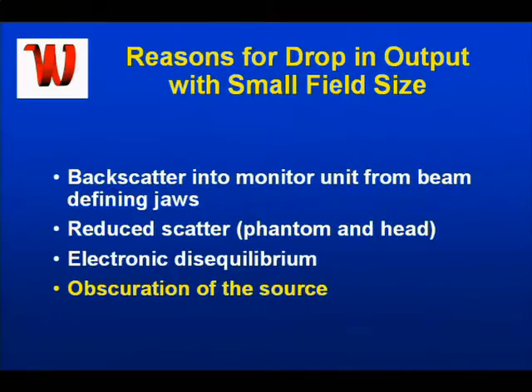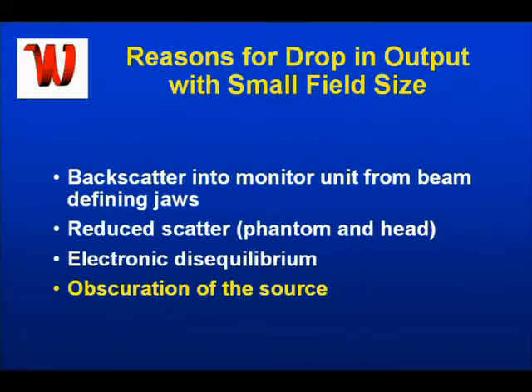What are the reasons for the drop in output with small field size? One of them is backscatter into the monitor chamber from the beam-defining jaws. There's also some reduced scatter, both from the phantom scatter and coming from the head directly. Electronic disequilibrium is also true, but really the major effect is obscuration of the source as you get down to IMRT sizes — you're actually seeing a smaller portion of the source, because the source in effect is a broad few-millimeter-sized object.